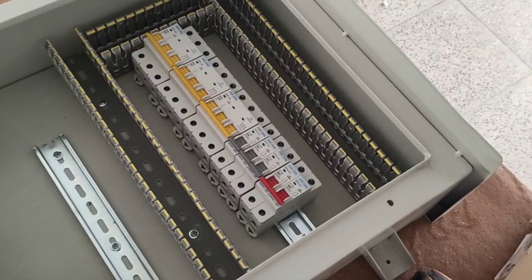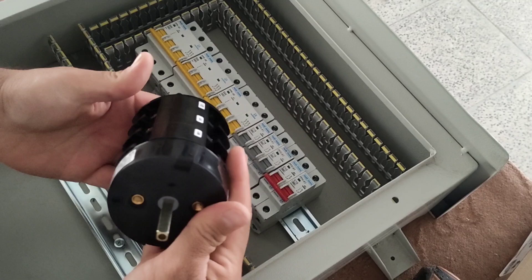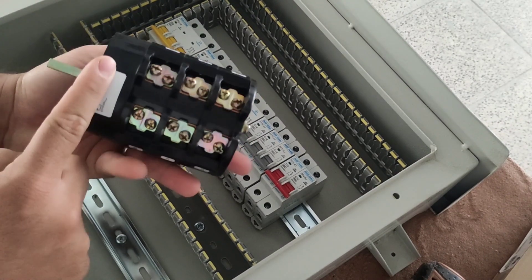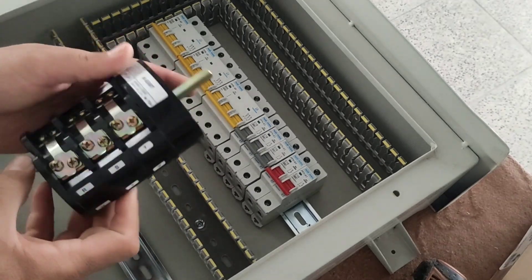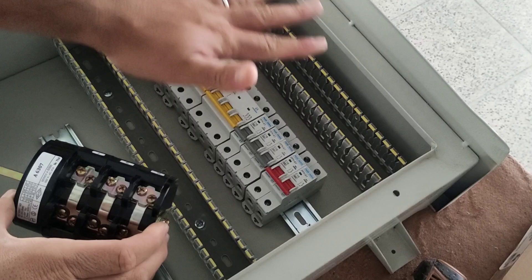Also in this electrical panel, a two-mode switch is installed for emergency power. From these three terminals, the city electricity enters the switch. And from these three terminals, the generator electricity enters the switch. And from these three terminals, the 3-phase electricity enters the electrical panel.